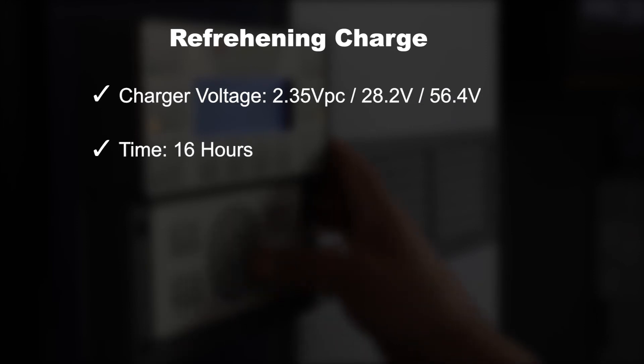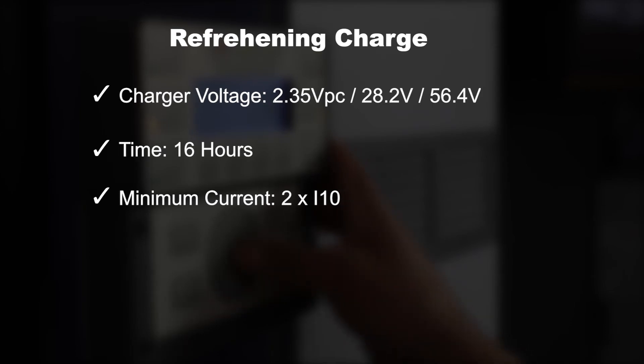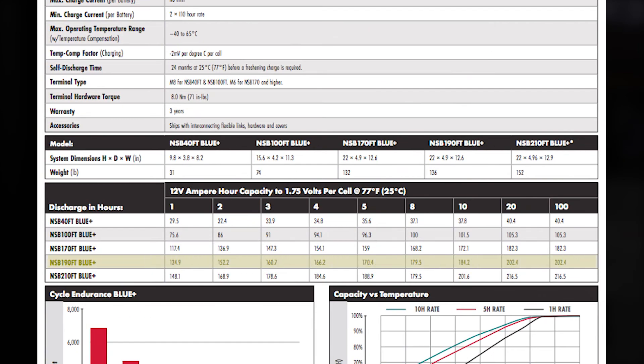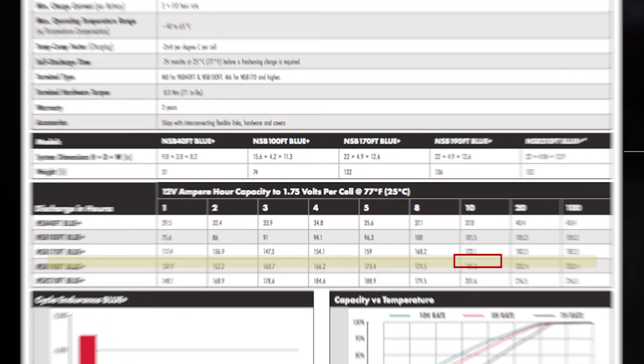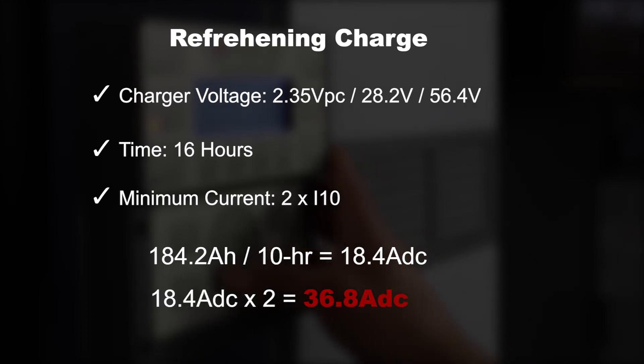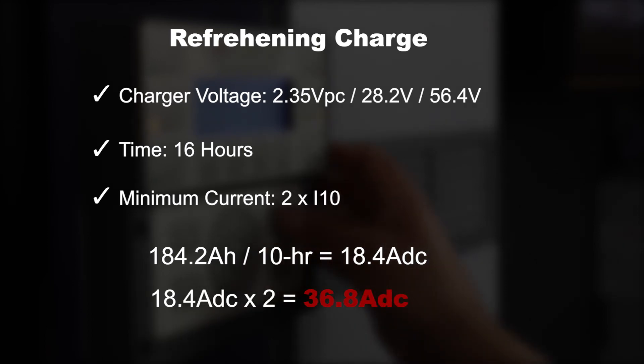NSB Blue Plus batteries do not have a current acceptance restriction; however, it is recommended to supply them with a minimum of 2 times the 10-hour rate. In our case, we are using the 190 amp-hour batteries that have a 10-hour capacity rating of 184.2 amp-hours. Dividing by 10 hours equals 18.4A DC; multiplied by 2 gives a recommended minimum charge current of 36.8 amps DC.